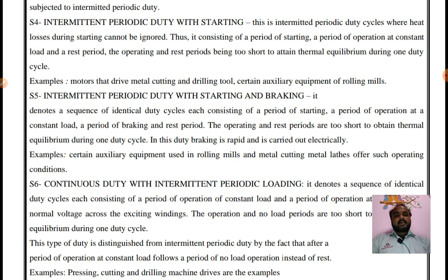It consists of a period of starting, a period of operating at a constant load and a rest period, the operating and rest periods being too short to attain thermal equilibrium during one duty cycle. So the losses during the starting period we will not ignore. Those losses will also be considered in this type of drives.